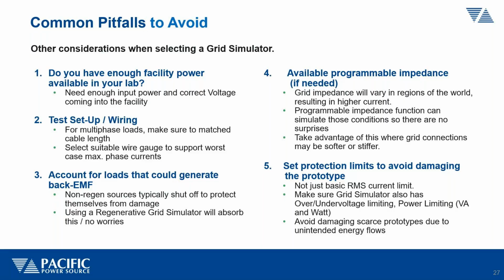Obviously, current RMS limit functions are typical on grid simulators, but there are other protections that you may want, such as peak current protection, for example, or power protection, and that can be either true power, real power, or apparent power. So you can set limits not just on current, but also on power levels and even voltage. Do you want to protect your EUT from overvoltage or check for undervoltage? You can basically make sure your grid simulator does not allow it to go over or under certain test settings and limits. So those are all aspects of protecting the EUT.